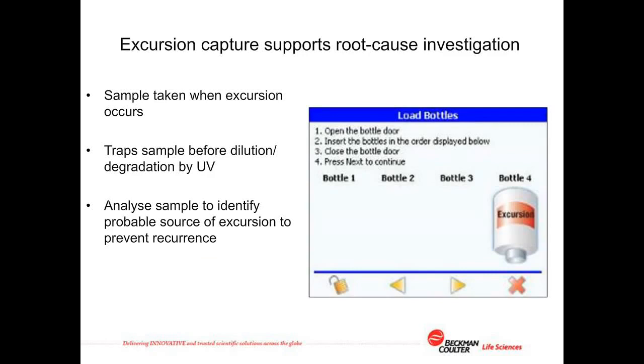As mentioned earlier in the presentation, TOC excursions can frequently be very short transient events. So the PAT700 supports root cause investigation into these TOC excursions by capturing a sample of the excursion into an empty excursion bottle, which is preloaded in the calibration bay. This can then be taken to the QC lab for root cause investigation to identify the possible sources of the contamination, hence supporting corrective action and preventative action, CAPA.